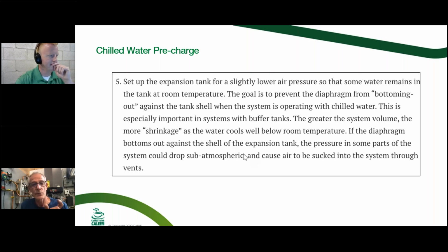As the water cools below the room temperature, the diaphragm can go down against that expansion tank, and now you could pull a subatmospheric condition, pull a vacuum in your system out there. And as Cody said, now if you've got an air vent somewhere in that system, a little float type, the float's going to go down, air is going to go in there, and you're going to start airlocking your system because you've pulled a subatmospheric condition and you're allowing air to go into your system. So that's why you want to have that little bit of extra capacity in there, as we know the temperature is going to drop below what your fill water temperature is.